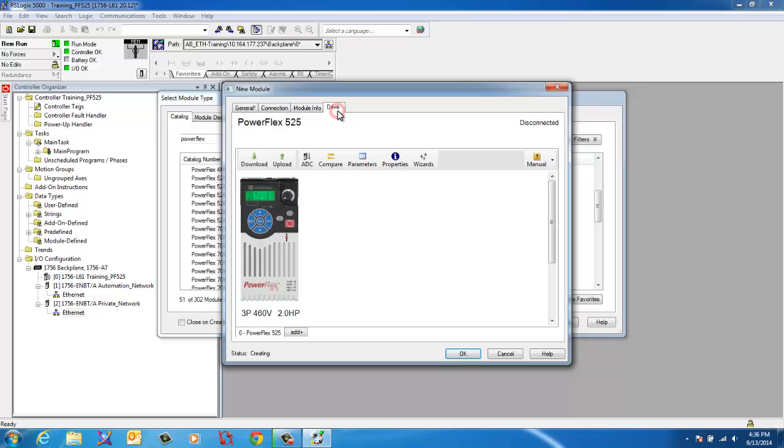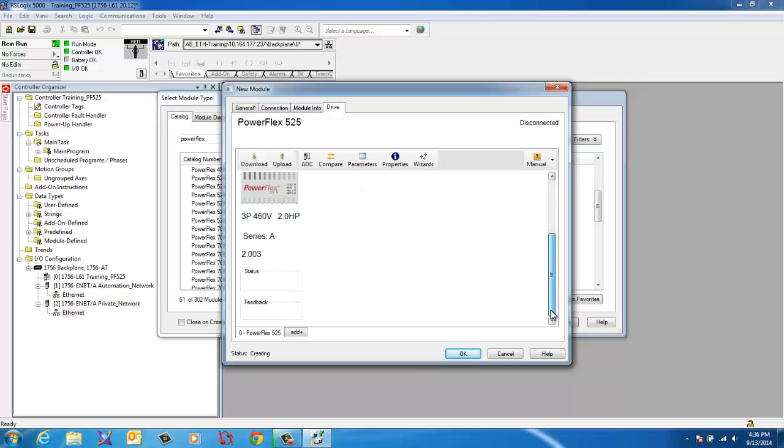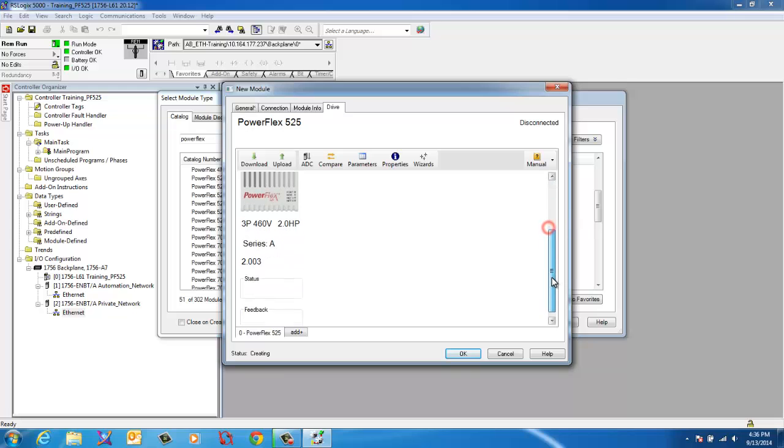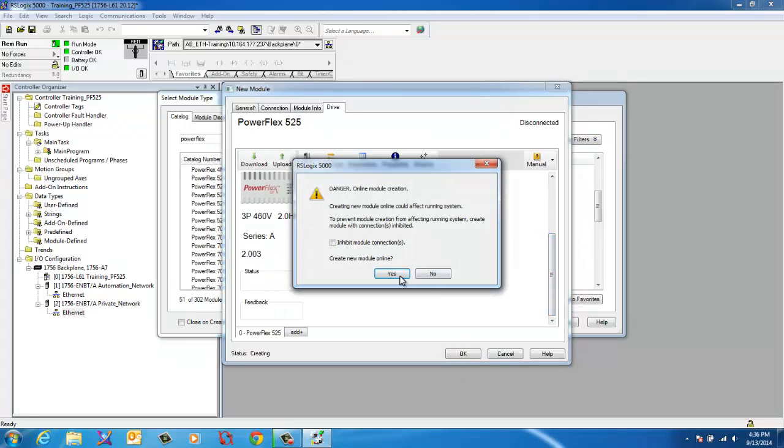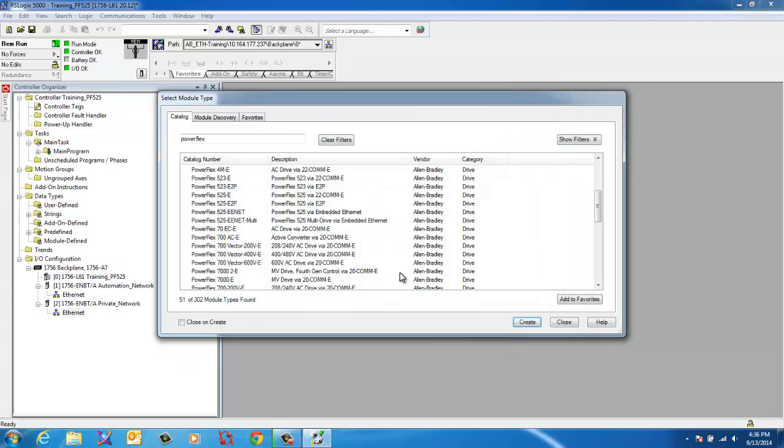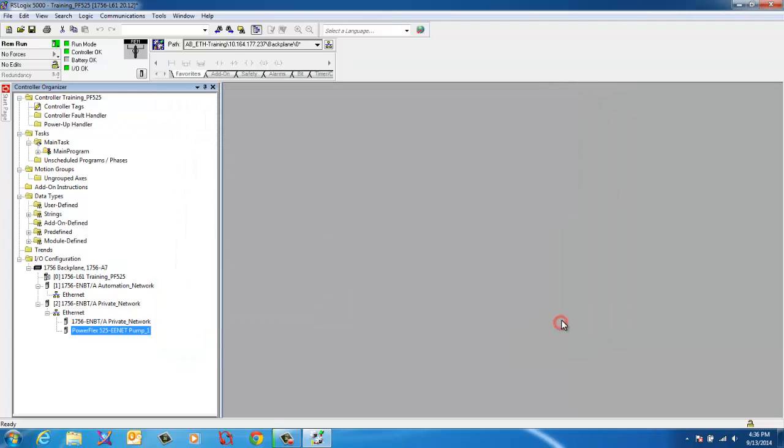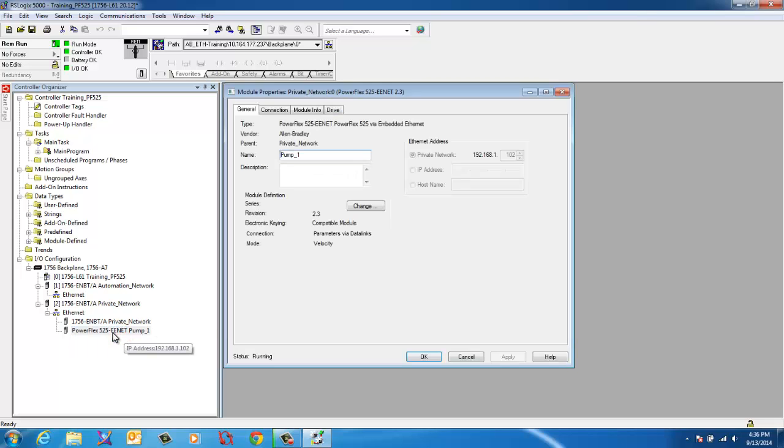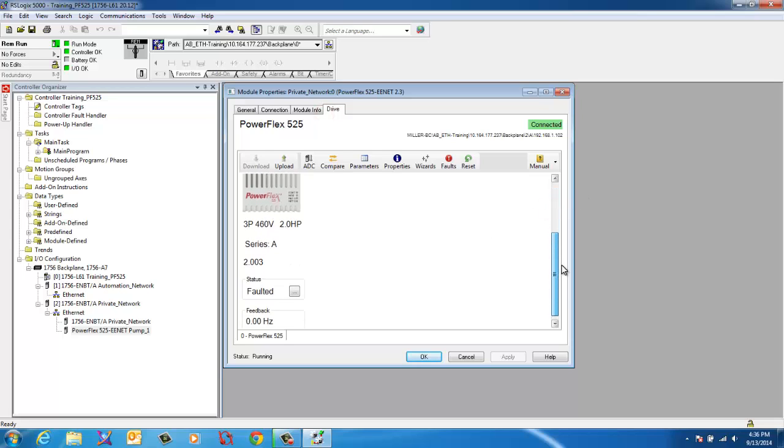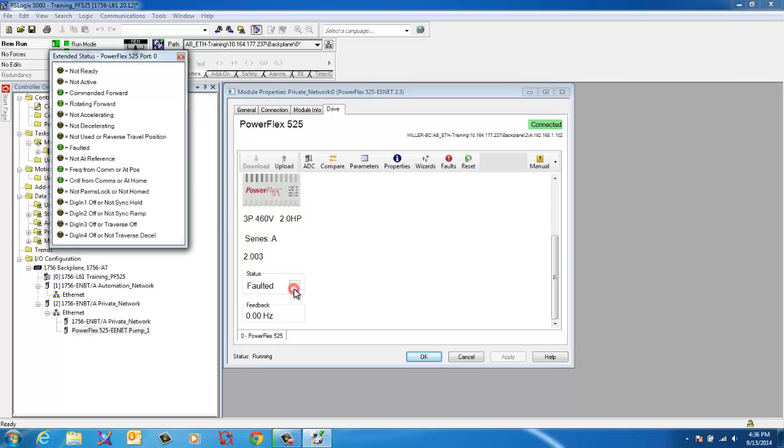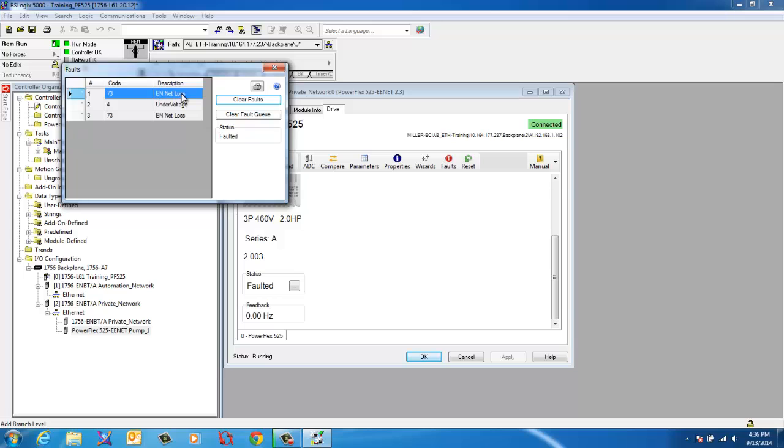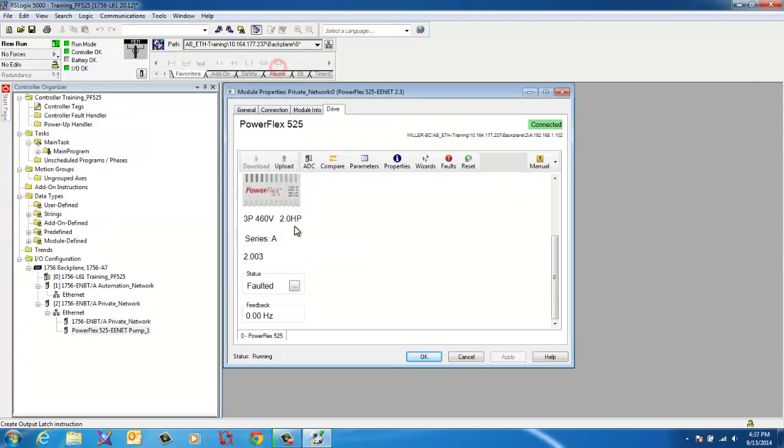Now if we go to the drive, we don't have to go online. It's already online because it matched everything. No status feedback. Nothing. We're not doing anything yet. Why? Because it's not finished in the project. So it's not going to populate anything. Hit OK. Yes. We want to go online with it. We'll close this but don't need it no more. Now that you've created your profile, now you can go back into it. Go back to the drive. And now it will update your statuses. It's faulted. Why is it faulted? We'll go to fault. That Ethernet loss. When we did a download to the processor it was already connected to another program that was in there. So it faulted under an Ethernet loss. We can clear the faults here. Clear the fault queue. We're not going to do that. We're going to do it through the program.